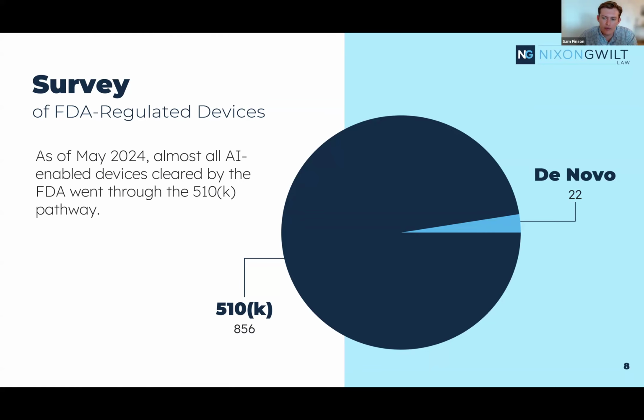Only 22 FDA-approved AI devices have gone through the de novo process. This is a much higher barrier to entry. What this essentially means is that there's no comparable predicate device in the market. You may need additional clinical and non-clinical data to support the claims throughout the filing process with FDA. And then a point I want to emphasize is that these figures don't cover all the devices or non-devices that are in the market that are outside of the purview of FDA regulation, right? So those that are clinical decision support or enforcement discretion, those that pose significantly low risk that they don't fall into either of these two pathways.